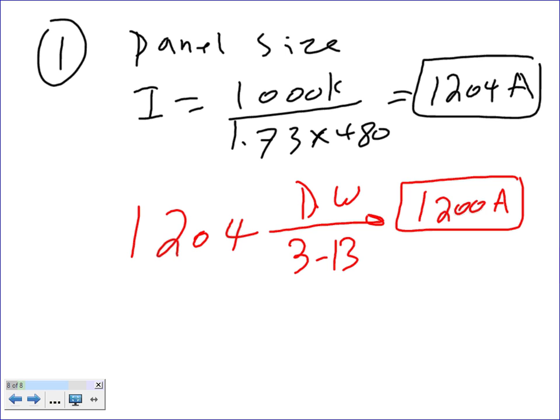What's the cutoff? Let me give you a cutoff. 10%. Use 10%. Really, 10% is a good cutoff. If you want a commitment, 10%. So if you are 10% higher than a panel size, go up. If you're 10% or less, go down. More than 10%, go up. Does that make sense? That's Chad's rule. I think it makes sense.